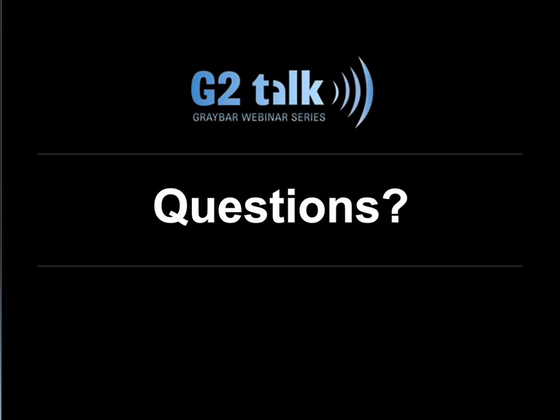Here's another question that just came in. Dave, can I retrofit TeSys T in existing motor control centers? Great question. Absolutely, yes. The design of TeSys T was actually done on size to replace existing either traditional or solid-state overload relays. As well, that device can be mounted up to 10 feet away from an existing motor as long as we can get the secondaries from CTs into the unit. So I can tell you that we've retrofitted every major brand of motor control center with this already. It's been very, very successful in doing so.